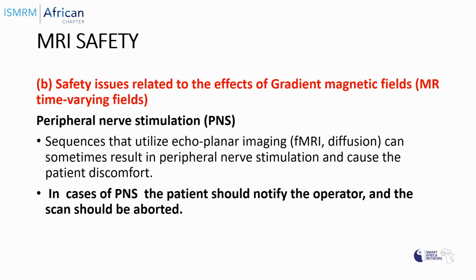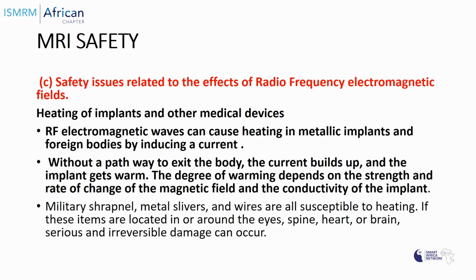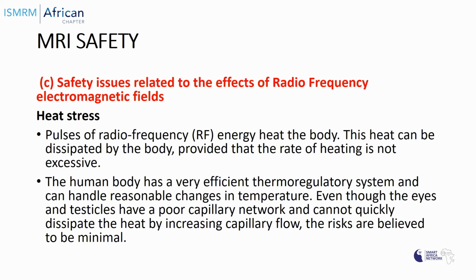Peripheral nerve stimulation is another effect of gradient magnetic fields, time-varying fields. In cases of peripheral nerve stimulation, the patient should notify the operator and the scan should be aborted. Heating of implants and other medical devices can also occur. Radio frequency electromagnetic waves can cause heating in metallic implants and foreign bodies by inducing a current. Without a pathway to exit the body, the current builds up and the implants get warm. The degree of warming depends on the strength and rate of change of the magnetic field and the conductivity of the implant. Heat stress can also occur.